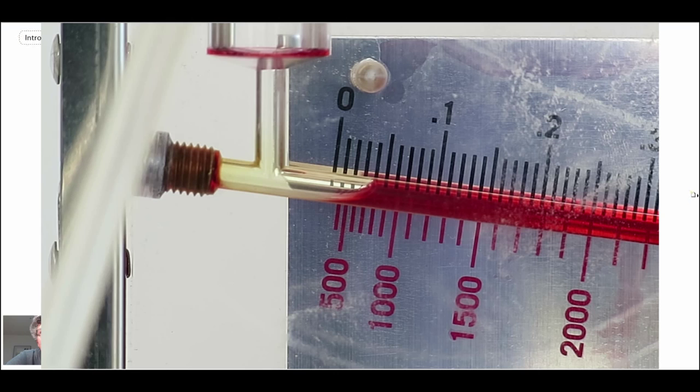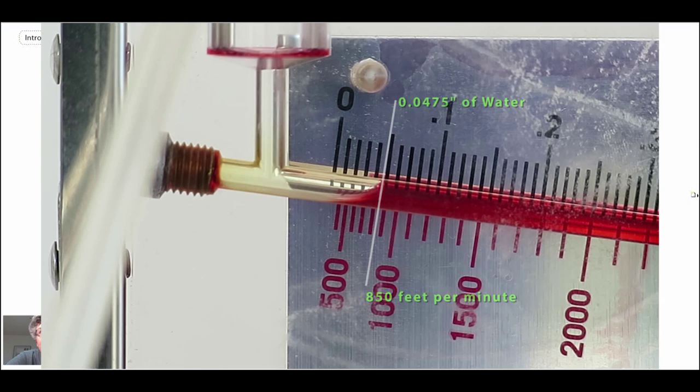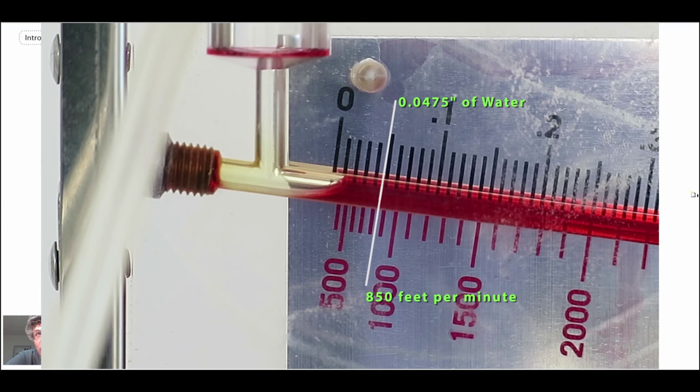We're going to measure that. We get 0.0475 inches of water. And with this incline manometer it's been calibrated at sea level, so that's 850 feet per minute.